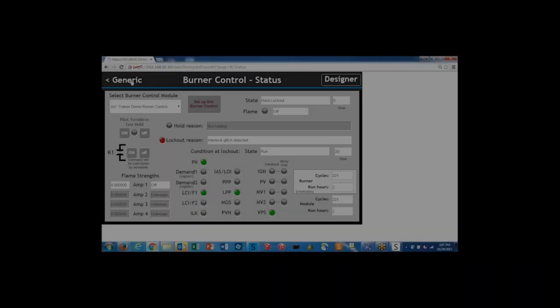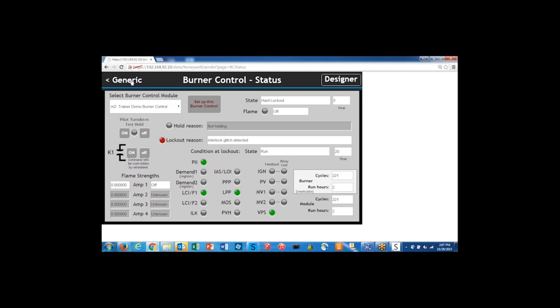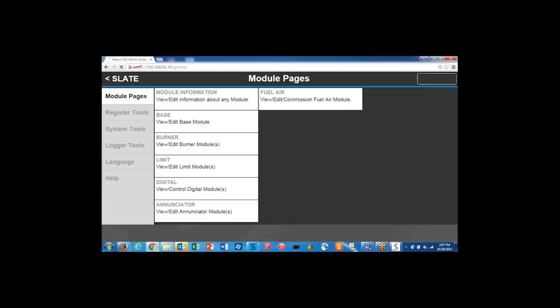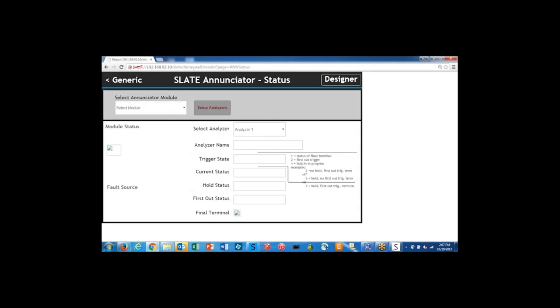On our burner control status screen, we see that an interlock glitch was detected and it caused a hard lockout of our burner control module. If we go back to the main menu and select the Annunciator module page, we can get detailed information on what actually caused us to shut down. We see here that the first out status was air flow switch, so the air flow switch is ultimately what cut us out.